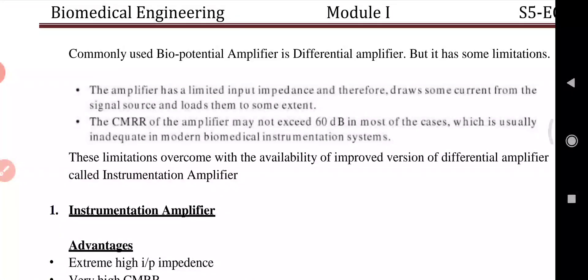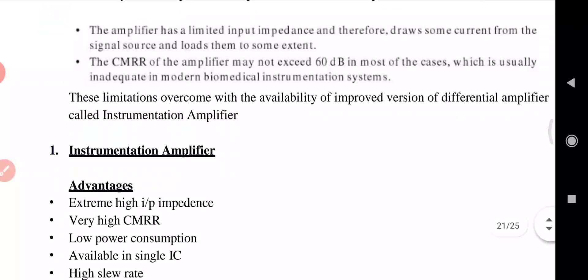Biopotential amplifiers also have some limitations. The amplifier has limited input impedance, and therefore some current is drawn from the signal source, loading it to some extent. Also, the CMRR of the amplifier may not exceed 60 dB in most cases, which is usually inadequate in modern biomedical instrument systems. We can overcome these limitations using an improved differential amplifier called the instrumentation amplifier.